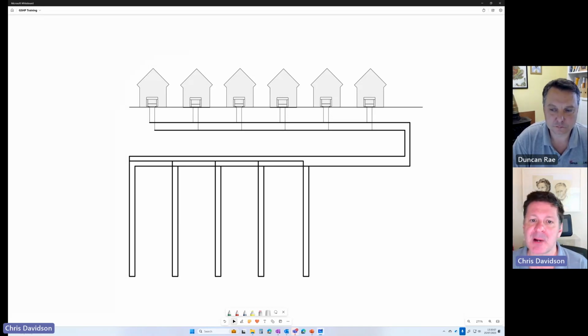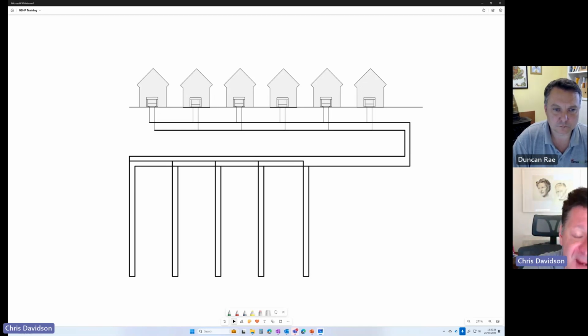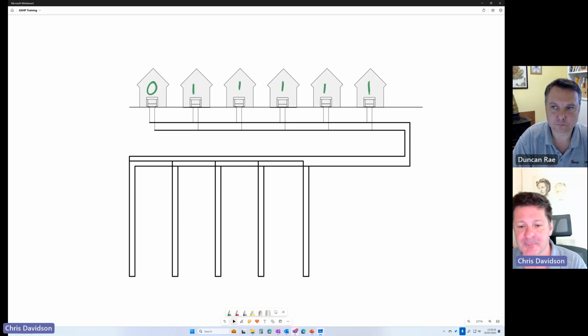And if we've got a number of buildings connected to the same ground loop, then if you imagine you're designing a 4-way electrical extension lead, you're not going to assume that you're going to have a 3-bar electric fire on all 4 sockets, or else your cable would be much bigger. It's a process called diversity. You assume that not everything's running flat out all the time. So we can take some diversity in terms of these ground loops and assume that not all of these buildings are going to be running flat out all the time. And that actually might save you a little bit of borehole.